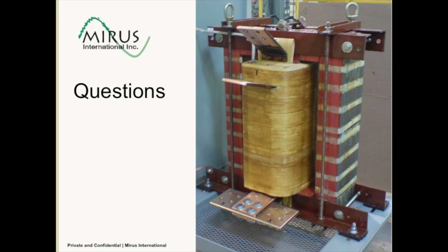The paper is entitled Right-Sizing Generators Through Harmonic Mitigation Realizes Energy, Emissions, and Infrastructure Reductions. It was presented at this year's IEEE Petrochemical Industry Conference in Houston, and it documents the application of our passive harmonic filters on an islanded pumping station where the generator had to be substantially oversized to handle harmonics generated by the pump's variable speed drives. And in fuel savings alone, the filter was paid back in about a month and a half. In addition, the generator was later replaced with a much smaller unit, lowering fuel consumption and emissions even further.